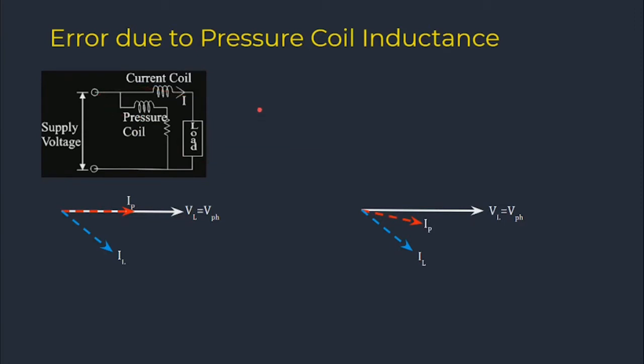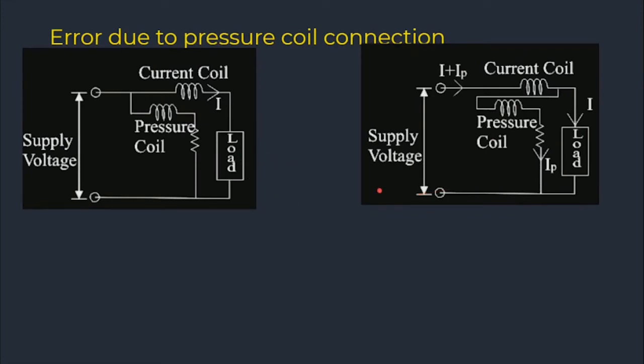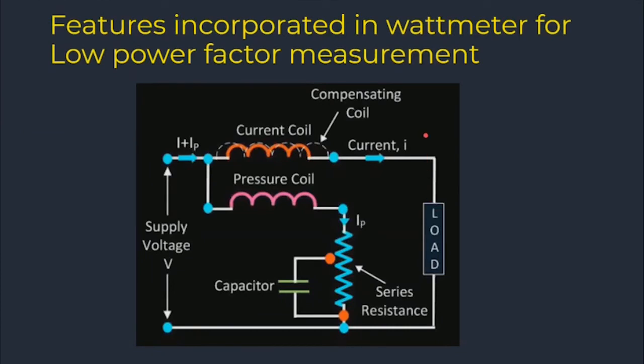Regarding error due to pressure coil inductance: VL equals V phase, and IP lags behind VL because of pressure coil inductance. The load current IL is also lagging. Ideally VL and IP should be in phase, but due to pressure coil inductance, IP lags. To correct this for low power factor measurement, a capacitor is connected in parallel with the series resistance to reduce errors due to pressure coil inductance and obtain correct readings.